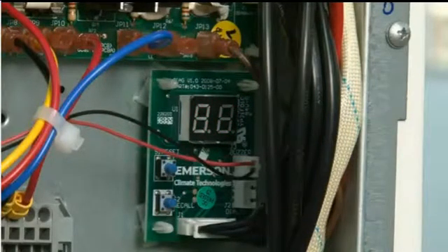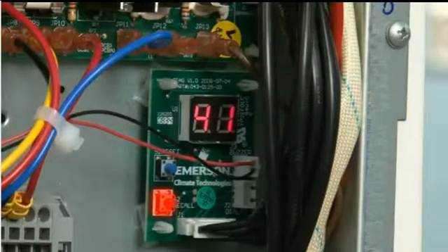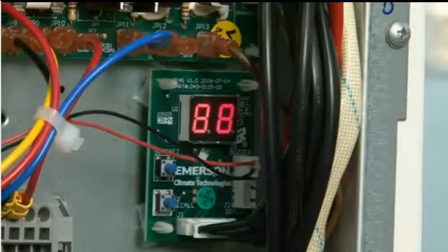Also located on the display board is a reset button and a recall button. The reset button will reset the display board only, and the recall button will display the last signal received by the display board. The very first display that you will see is an 88, a 02, a dash and an F for medium temperature, or an L and an F for low temperature, and a 00. This identifies the software version, the ID code, and that the power is on.